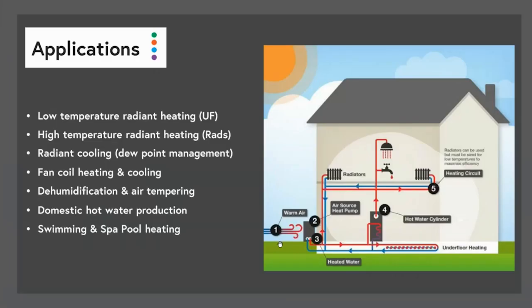Right, let's move along to applications. So monoblock heat pumps that produce hot and cold water. What can we do with them? Well, we can do a whole lot of things, which are all listed there. We can do low temperature radiant heating, so that's underfloor heating. We can also do high temperature radiant heating, so that would be things like ceiling panels, which are getting very popular in commercial applications and in residential heating in Europe.